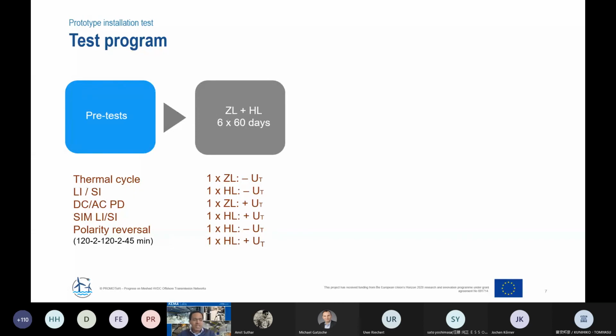This long term test is divided into different testing blocks, 6 testing blocks. Each testing block lasts for 60 days, as you see here. These blocks are at different loading conditions. That means there is a zero loading, which means there is no current flowing through the bus bar, but only a voltage applied to the system. And there is high load. At high load, 4,000 amps of current is running through the bus bar.